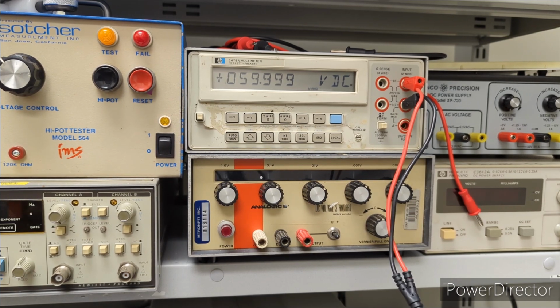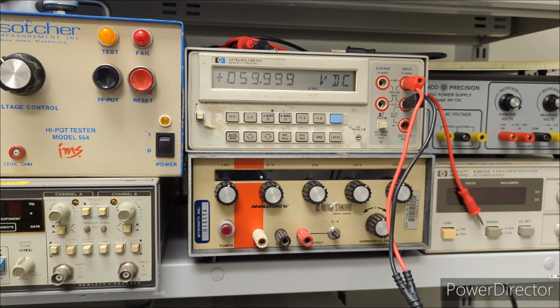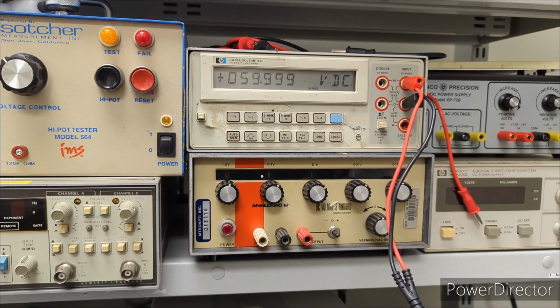Okay, so now it did drop about 8 millivolts, I'm sorry. But you can see it recovered right back to where it was. Now, that load effect doesn't count that drop. That's the transient. So if it was out of spec, it would now be sitting at, for example, 59.993 or lower. And you can see it's returned right back to where it was without a load. So that, again, is a good indication that the instrument is operating within spec.